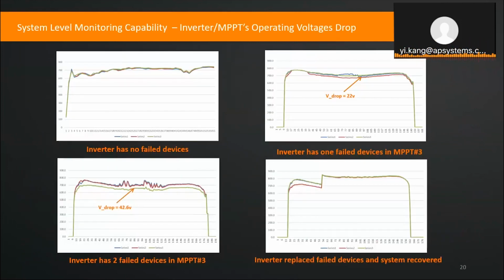How to monitor the device? A lot of people ask me if your RSD device has the function of monitoring each module's performance, or is it just to know your RSD is functional. No, our device follows the strategy of being as simple as possible. If you add a monitoring function, it gets more complicated, with lower reliability, even a higher failure rate. So we decided no, we go with the simple and more solid solution. But it's very easy to monitor just by monitoring the string inverter MPPT portal.